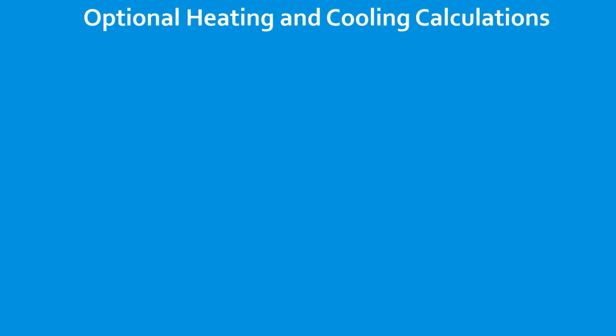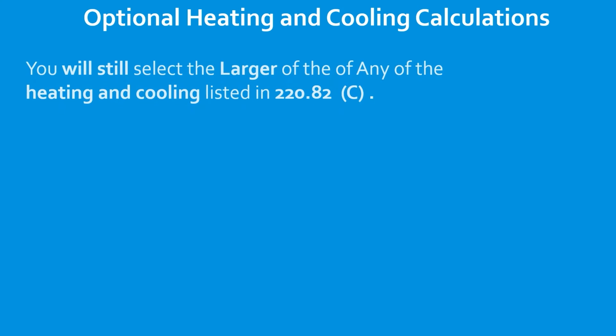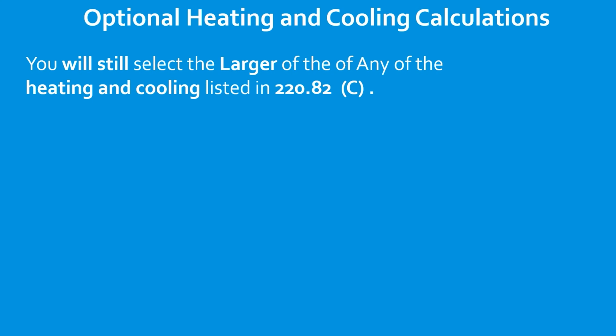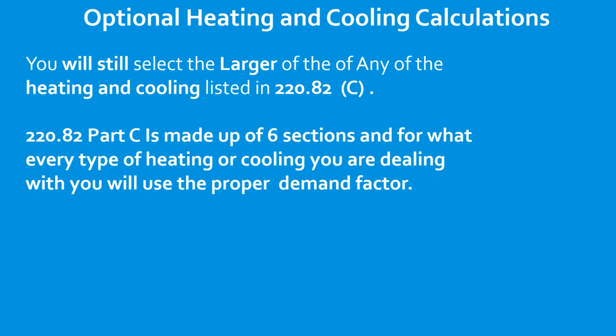Okay, let's look at optional heating and cooling calculations. You will still select the larger of any of the two that are listed in 220.82C. If you want to take a minute, pause the video, read that part now. 220.82 Part C is made up of 6 sections. For every type of heating or cooling that you're going to be dealing with, you just use the proper demand factor listed in that section.